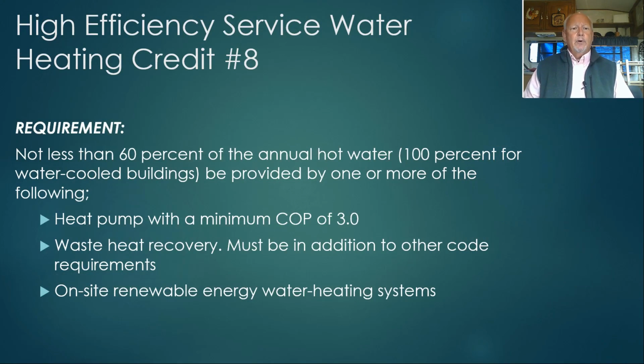So what is the requirement? For credit number 8, not less than 60% of the annual hot water use, or 100% for water-cooled buildings. So if you have water-cooled HVAC equipment, it shall be 100%. This must be provided by one or more of the following: either a heat pump system with a minimum COP of 3.0. We saw earlier that in our high input water heating systems, the minimum COP was 2, but in the additional efficiency credit option, it's 3. Or waste heat recovery, in addition to other code requirements.